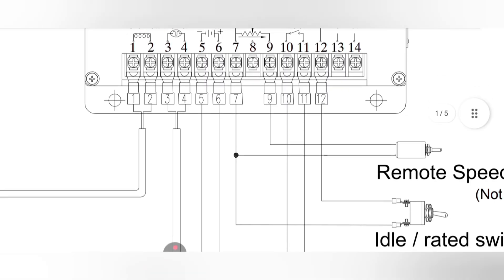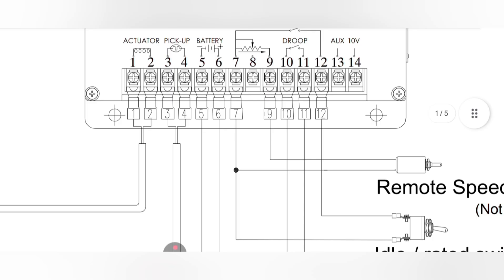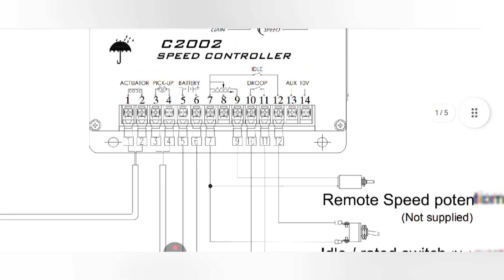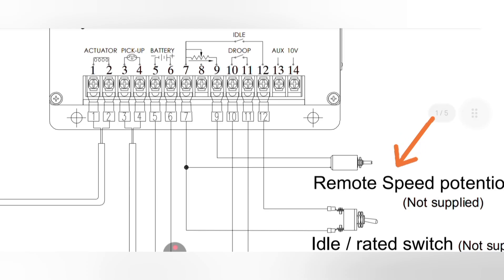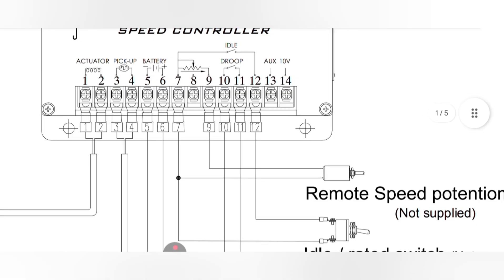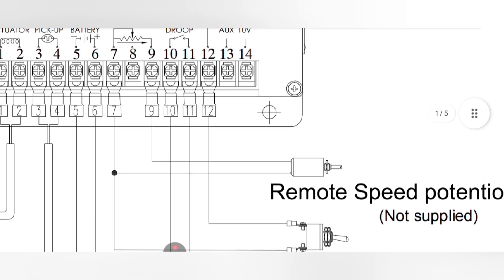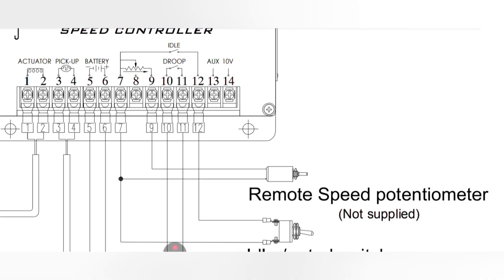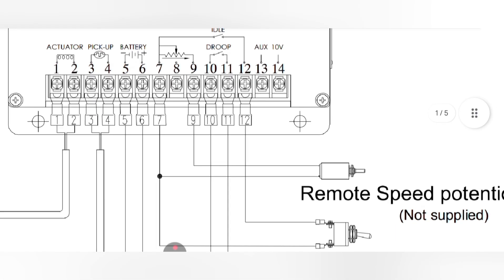Pin number seven and pin number nine are for the remote speed control potentiometer. We can remotely control and adjust the generator speed through this potentiometer from a long distance — for example, 20 or 30 meters away from the generator. By rotating the potentiometer clockwise or counterclockwise we can increase or decrease the engine speed remotely.